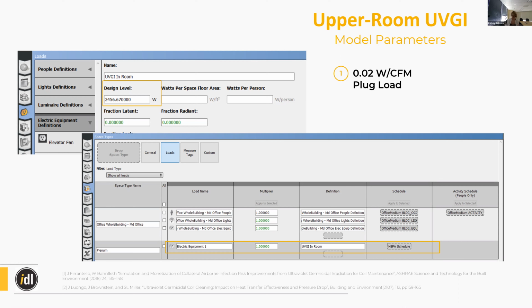So higher energy costs, but the really big one with this is the capital costs, because those lamps are so expensive. It just takes a lot to buy them and also to install them correctly. So that's the big one with this. UVGI in room is very effective when installed right, but you have to think about reflective surfaces and lamp degradation over time, stuff like that. Great for use in hospitals or operating rooms, places where you really do need things almost completely disinfected, but just because of that high capital cost, that's why you don't see them very often in other situations.